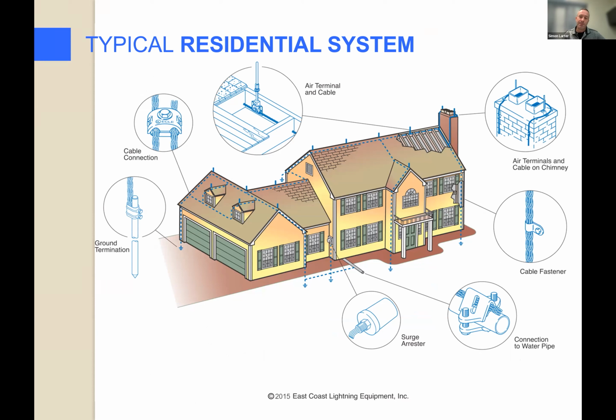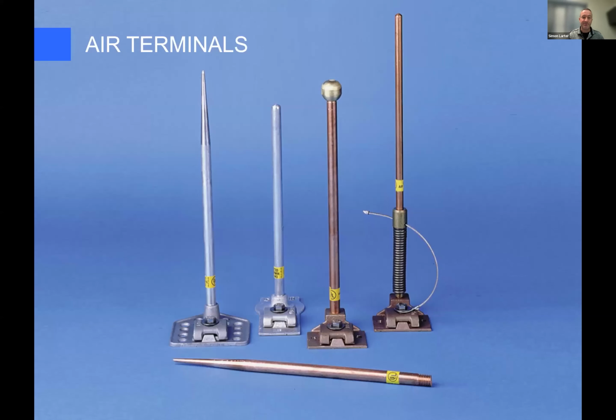So even on this, I guess that's a mid-sized family home, you've still got a number of lightning rods across the ridges, on the garage, on the dormers, on the chimney. It's the same 5 elements, however. You have lightning rods, you've got interconnecting conductor, you've got bonding connections, you've got grounding, and you've got surge protection. Those are the 5 elements in any system: commercial, residential, industrial, military, whatever you want. Any kind of structure is always going to have those 5 elements. Air terminals. There we go.